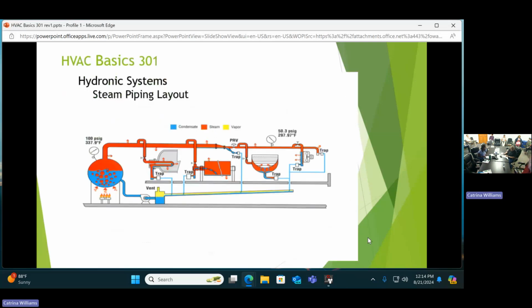Now, instead of the steam kettle, now we have a boiler. It's a true pressure vessel. And this slide shows 100 psi, but it works the exact same for 15 psi. The fire heats up the water, it bubbles and turns into steam, and runs through the piping. Now keep in mind, unlike a hydronic hot water system, where you have to pump that water through there because it's a fluid, when it turns to steam, you don't need a pump. It flies through those pipes. And you can have a pressure reducing valve and drop it down to a different steam pressure, like 5 psi, going into a fan coil unit or a unit heater.